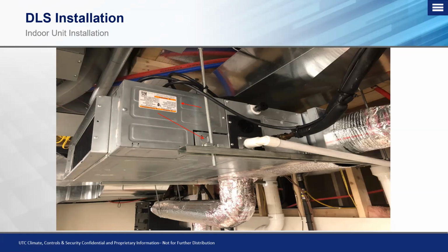Now, unfortunately, in this case, you can see on the bottom side, they drilled into the bottom side of the unit and tapped out, and they also have the same situation on this side here with their supply air. So in this case, in order to correct this, not only do we have to patch the holes that they cut on the bottom side of the unit, but now we have to unhook the unit, reinstall it the correct way, hook up the drain line properly, and then make sure and retest that the unit is giving the proper amount of CFM and BTUs to condition the space.